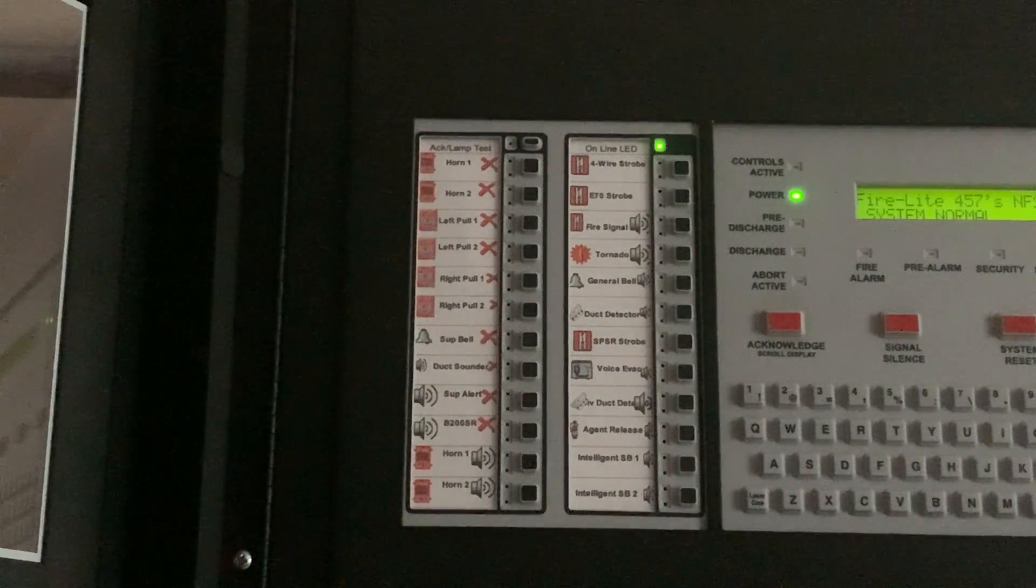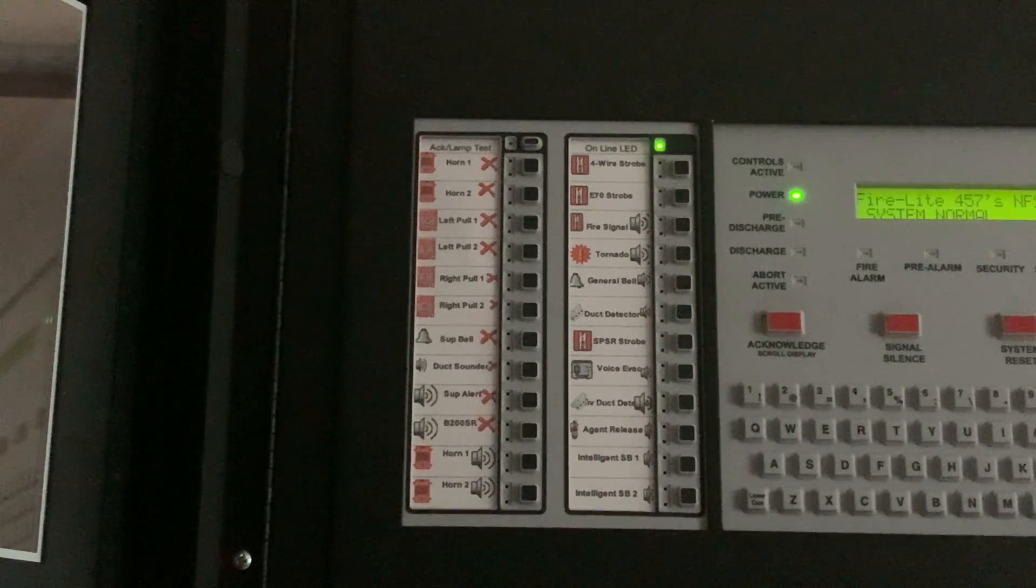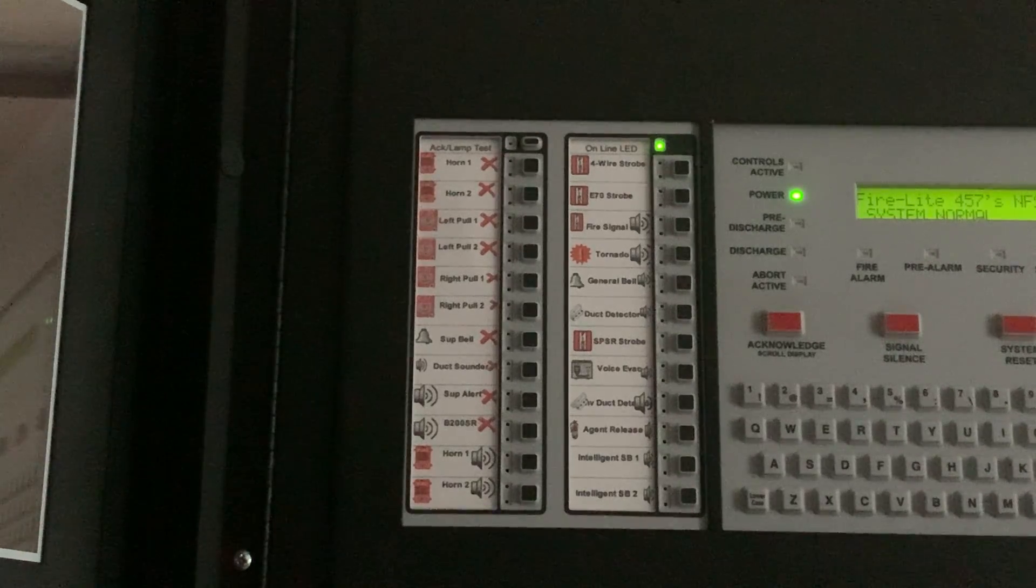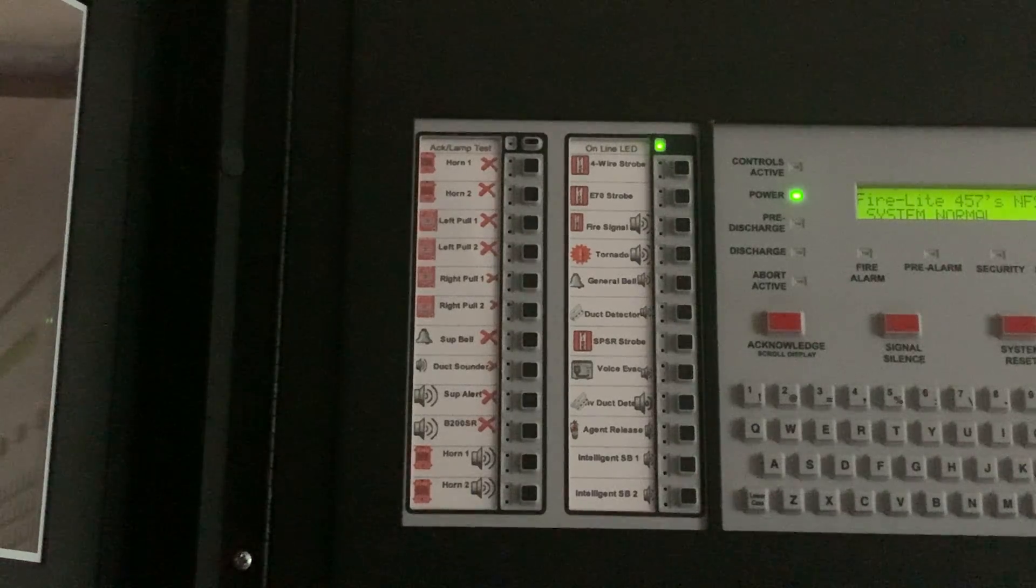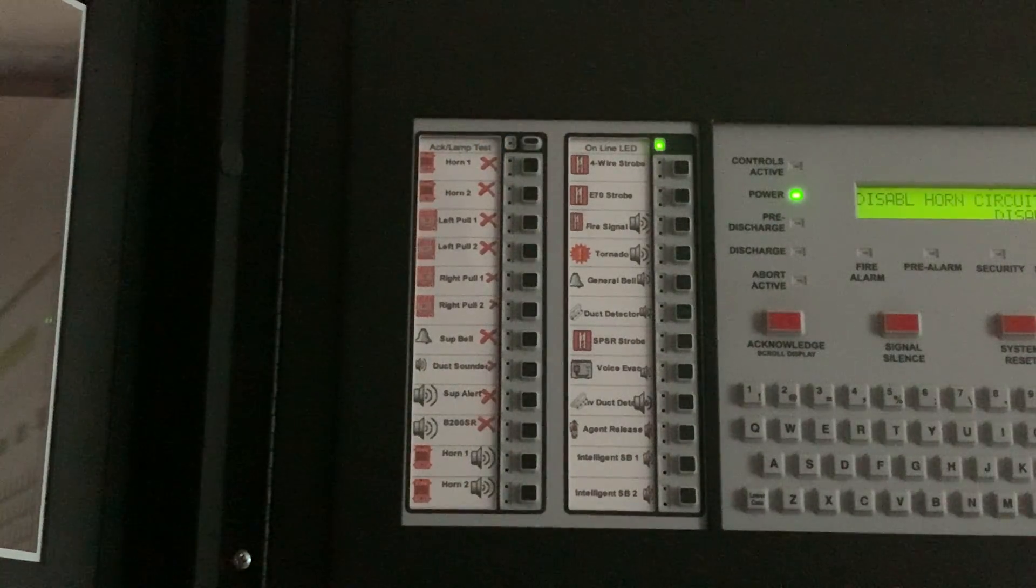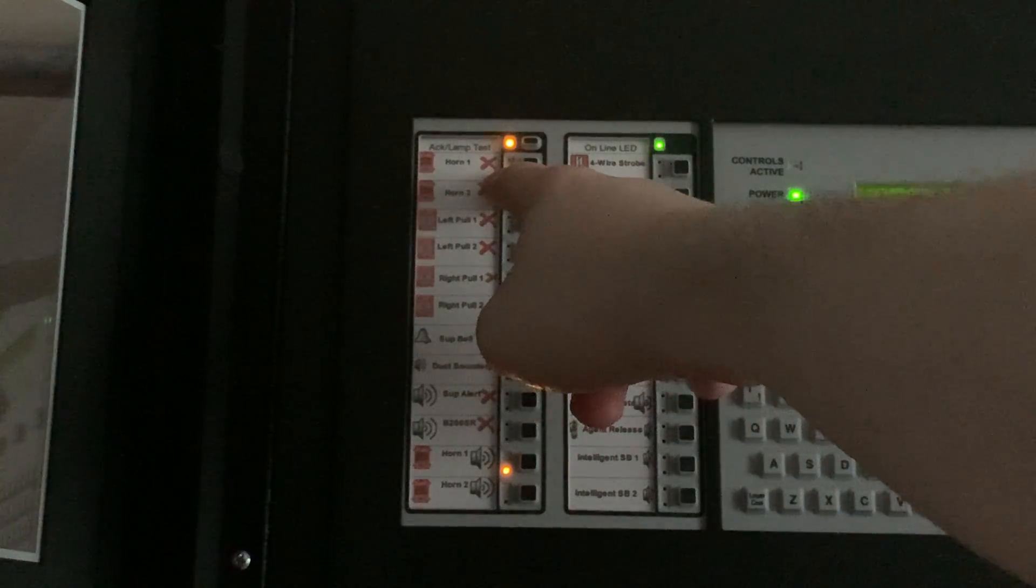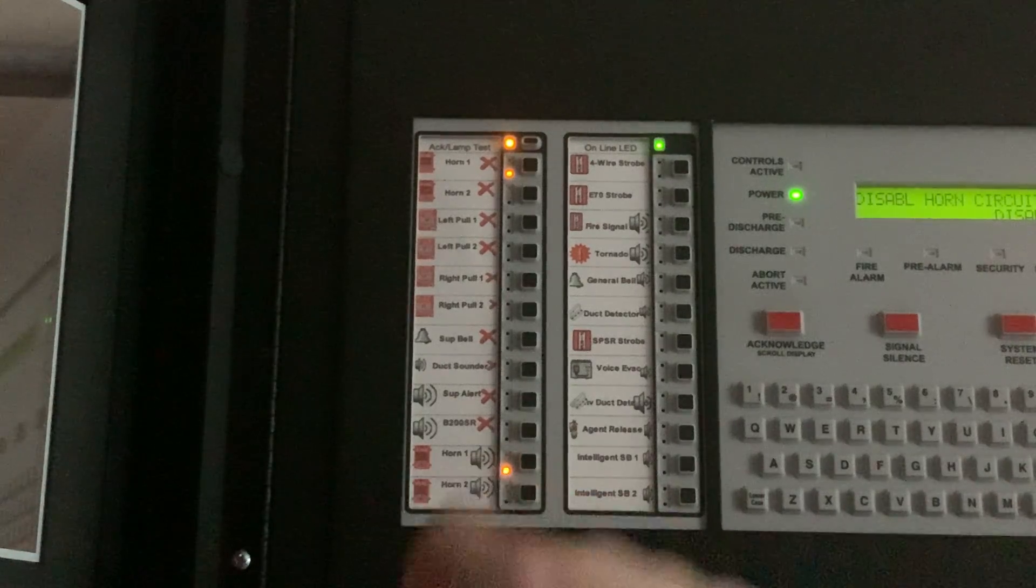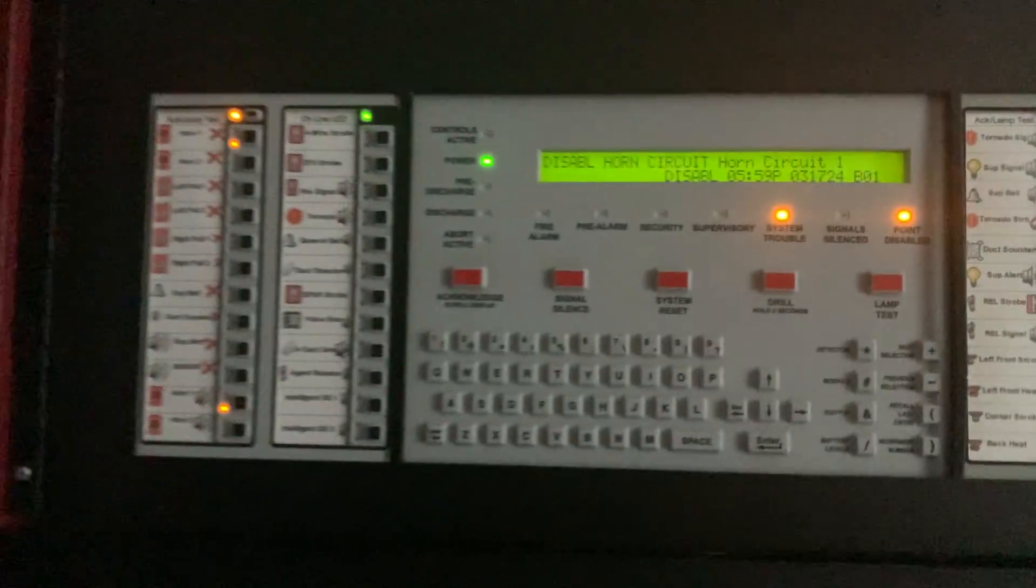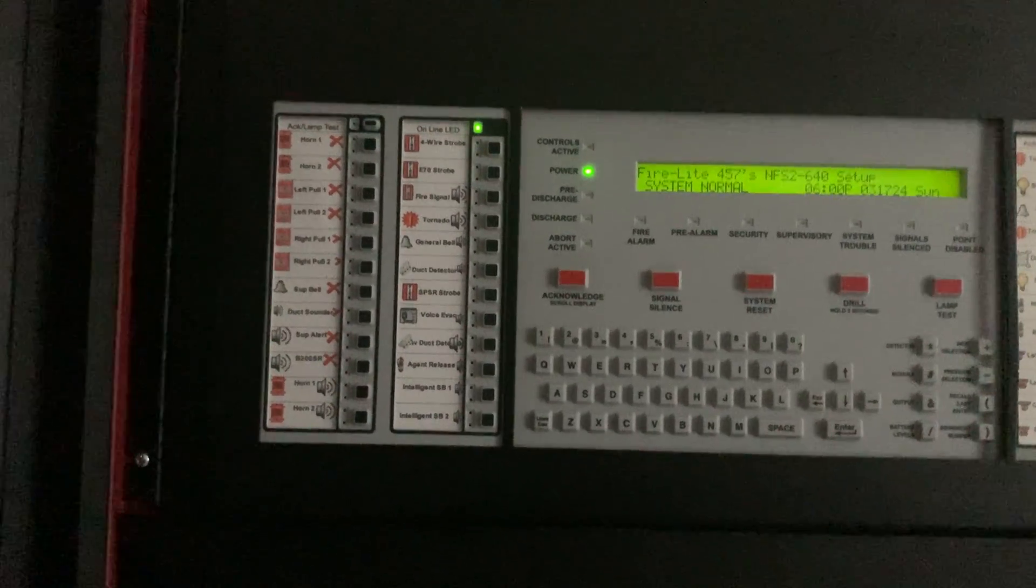So any disable switches, I have programmed to light up red. And all the control output switches, I have programmed to light up green. So first, we're going to go ahead and start with NAC 1. So when I press this button, the trouble LED for NAC 1, as well as the trouble LED for the control switch on NAC 1, both light up. See right here, the horn circuit one is disabled. And now when I press it again, it'll go back to normal.